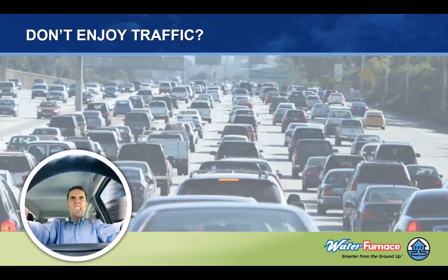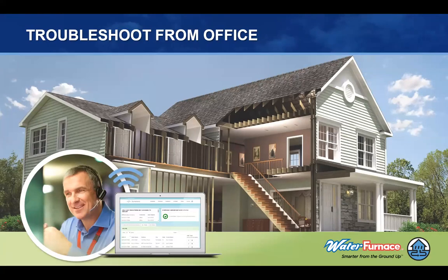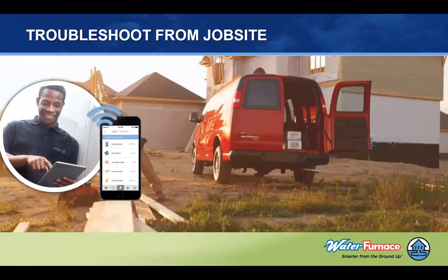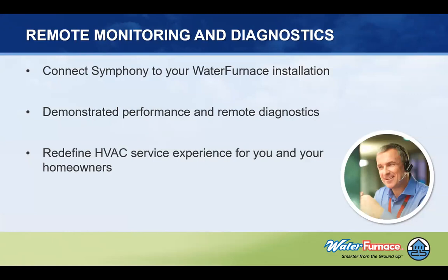So the key is, none of us like to drive to a job site. The Symphony system, with all of the parameters that we offer, allows you to troubleshoot from the office or from the job site. It makes it so that you don't have to travel in order to fix an issue, and it also prevents the homeowner from having to schedule with you. So remote monitoring diagnostics: connect the Symphony system, get all of the sensor kits that we offer, and you get demonstrated performance and remote diagnostics. And we believe it really changes and redefines the HVAC service experience for both the contractor and the homeowner.